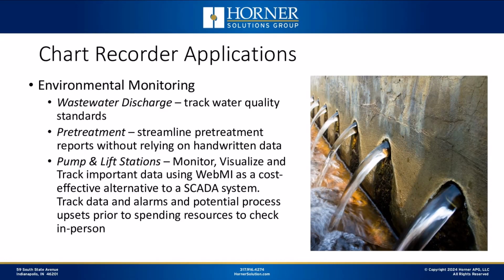There's just a lot of convenience for this sort of component, especially when you think about the fact that if it's a facility that doesn't have a SCADA system already existing, this is a much more inexpensive approach than a SCADA system might be, and especially easy to get up and running quickly. You've got a single box, you install the box, you wire your sensors, you set a few parameters from the touchscreen, and away you go.